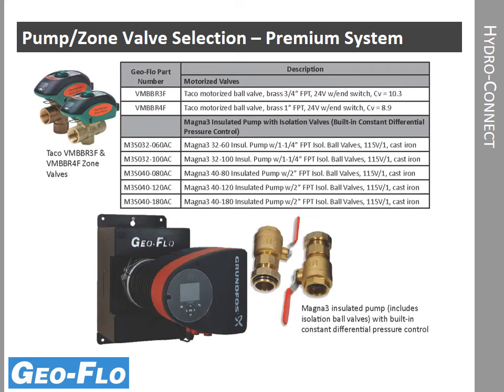On the hydronic side, whether it be radiant floor or fan coils, we can go with the premium system, which is variable speed in this case. We have a Magna 3 pump that would deliver flow to the various zones, and we'll choose a motorized valve based upon the zone manifold or the fan coil unit. When we set the system up initially, we would open all of the zone valves and set the Magna 3 maximum pressure. That gives us the flow rate when all of the zone valves are open. As the system is operating, then the zone valves are opening and closing, and the pump is speeding up and slowing down accordingly. The zone panel actually has a switch that enables the pump anytime there's a call from any zone.